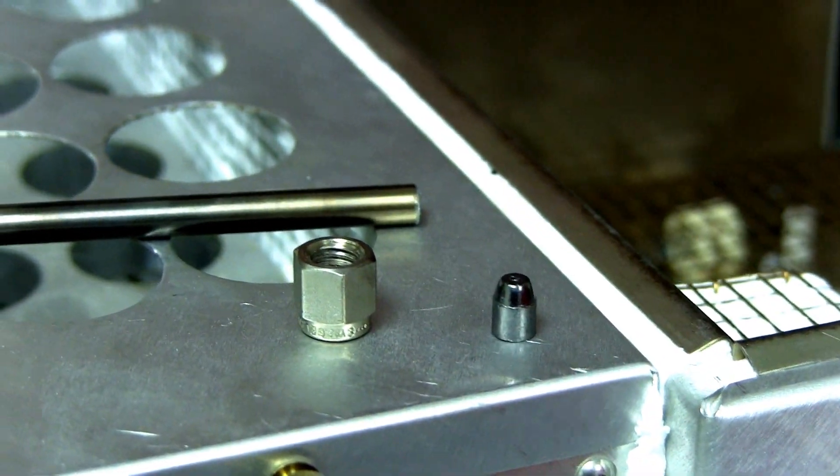If that's the case, you need to find some kind of little tool. A little dentist pick works really great to poke into that soft graphite ferrule and then pry it out. You should be able to feel that the fitting is not clogged up with any kind of graphite ferrule from the previous installation.